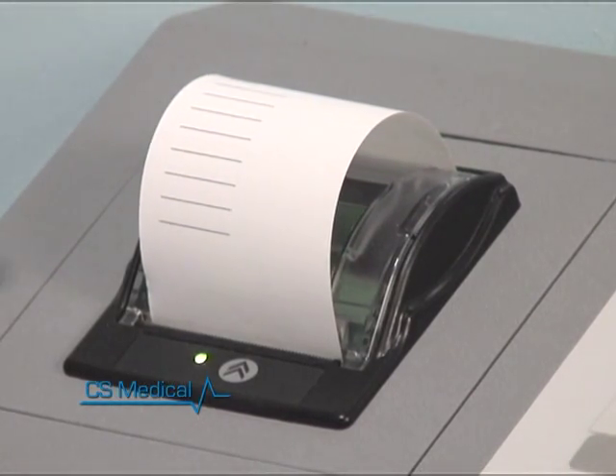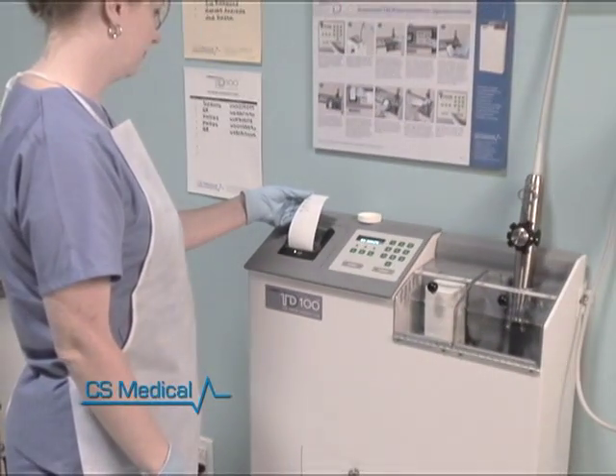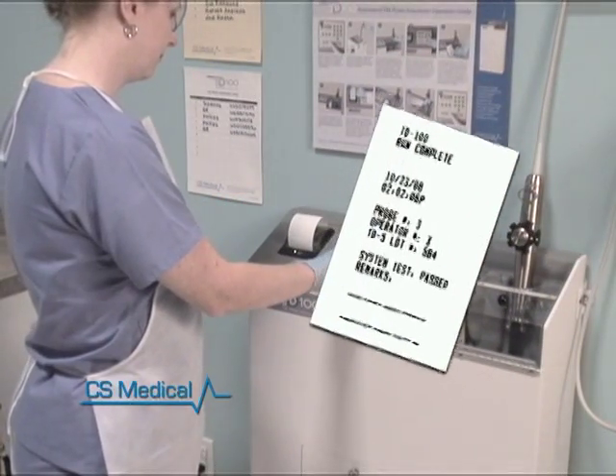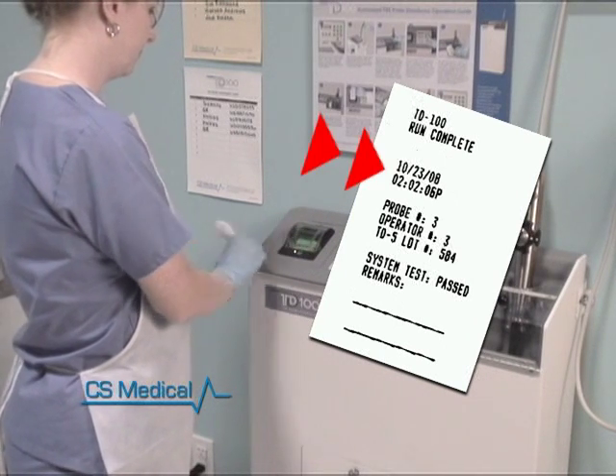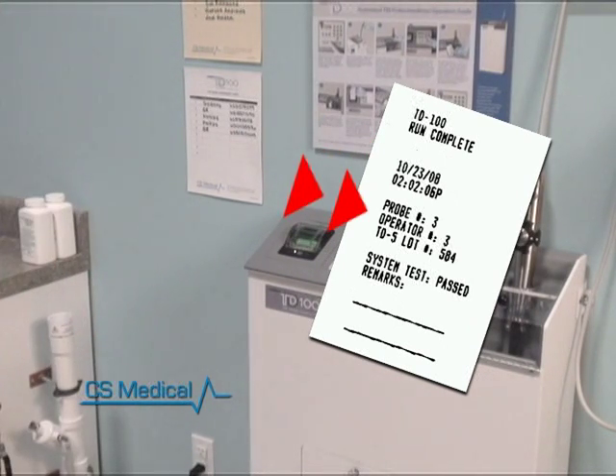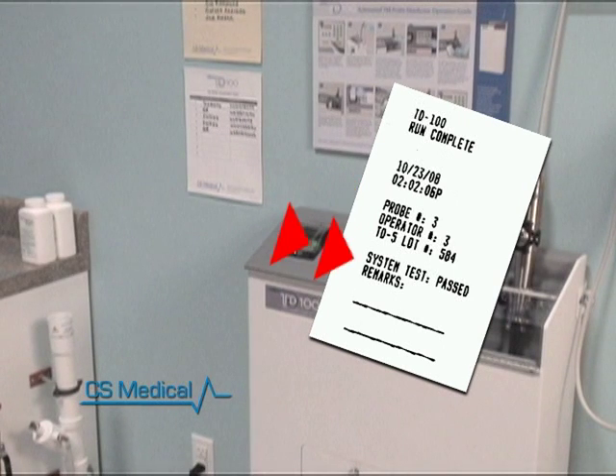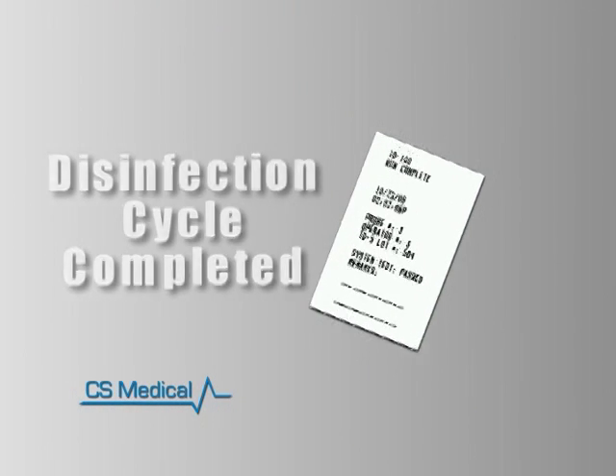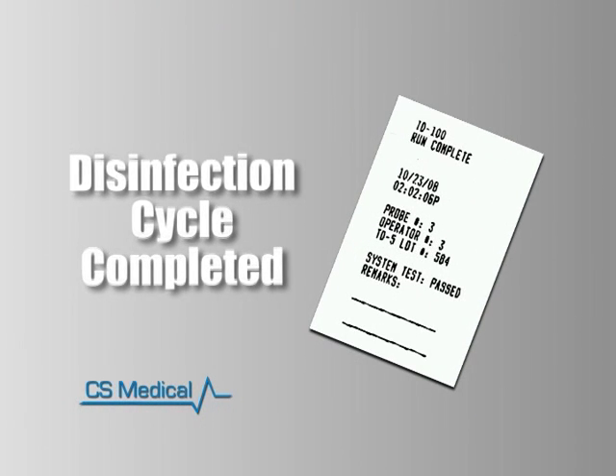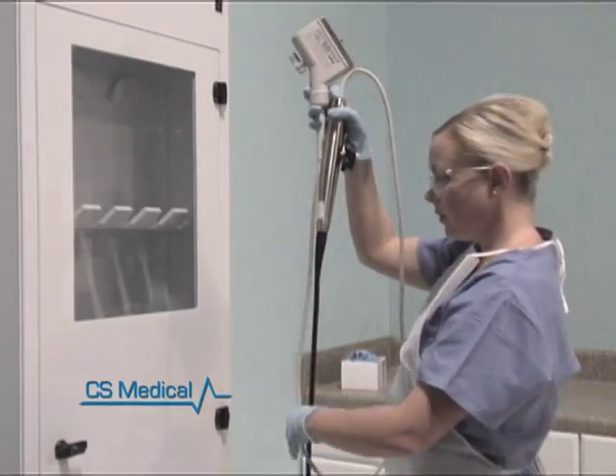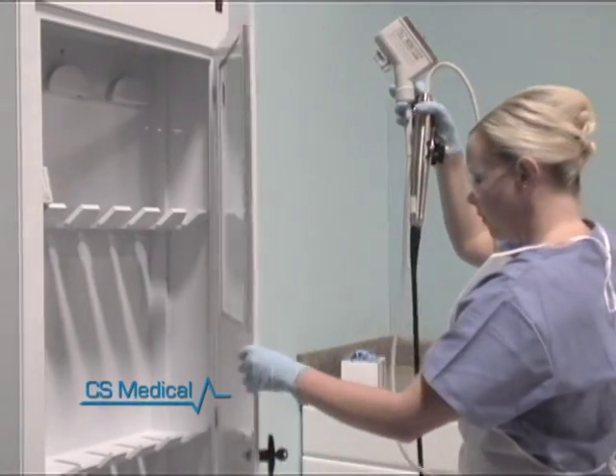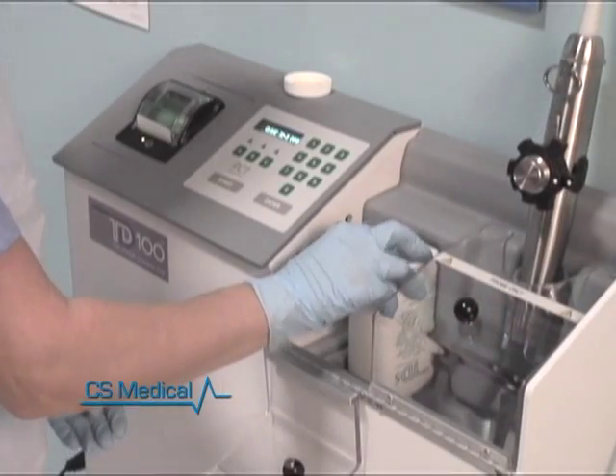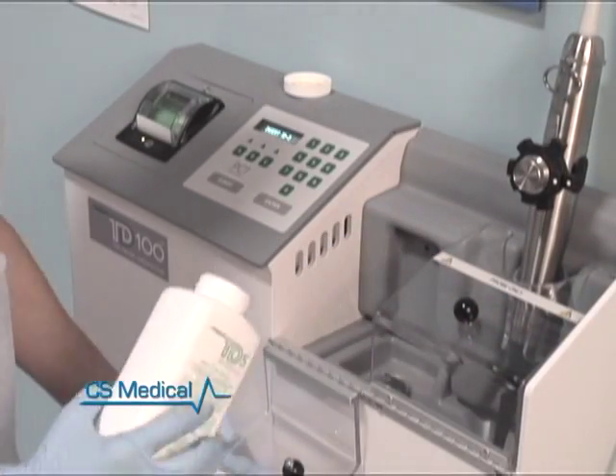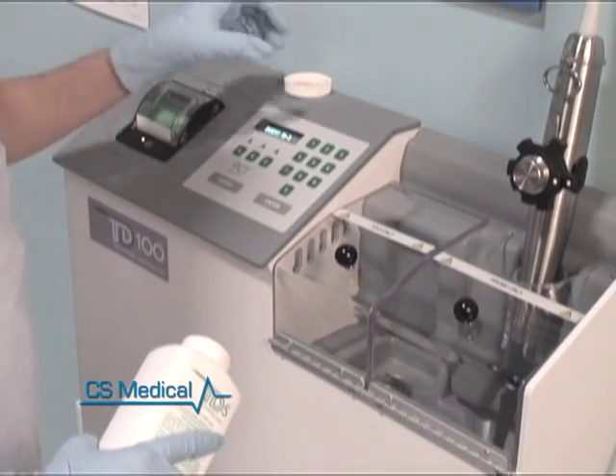Let's take a look. At the end of the cycle, a beep alerts you that the printed receipt is generated. As you can see, the report has the time and date of the procedure, as well as the probe number, operator number, TD5 lot number, and diagnostic test confirmation. A valid disinfection cycle has been completed, and the TEE probe is ready to be removed and prepared for reuse or storage. Once you accept the printed validation report, the TD100 will take you through the steps to safely remove the empty TD5 bottle and the disinfected TEE probe.